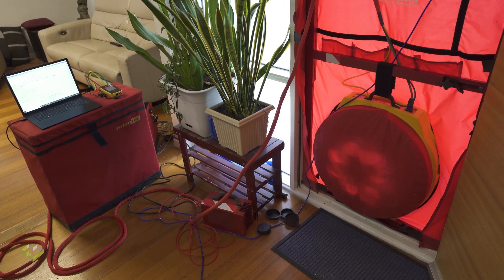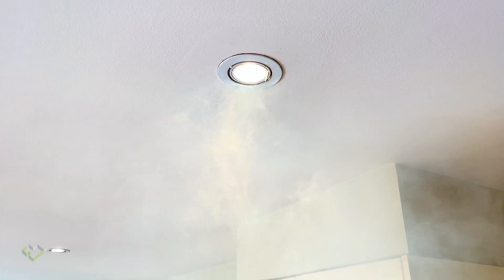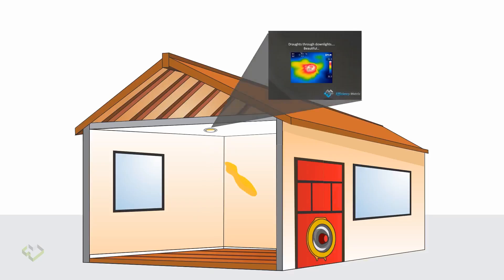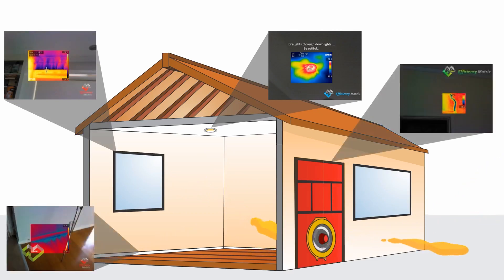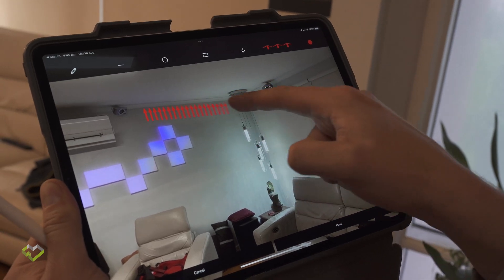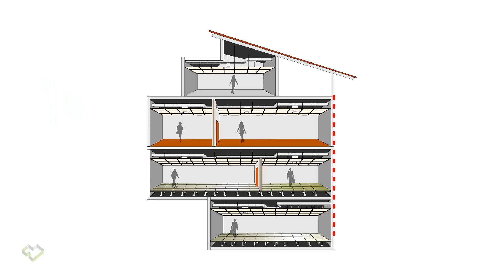With an air tightness test, especially in negative pressure, we can force air out of all the gaps and holes within the building envelope to find issues, but also document where those issues are. With that total airflow through the building envelope, we can then quantify how airtight a building envelope is — represented either as an air change per hour value at 50 Pa, or a permeability rate, which is how leaky every square meter of the building envelope is.